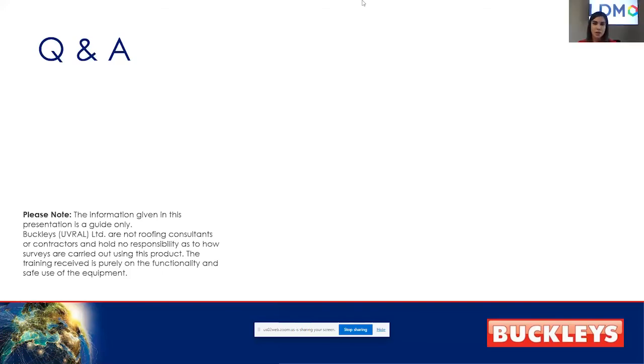One more: is there any preventive maintenance to consider? These machines, we do say on a 12-monthly basis you should have checked. The dry machine is a calibrated piece, so it is recommended every 12 months you get that service. We do recommend the wet machine is done at the same time - that's more of a certification test to prove the outputs, really.